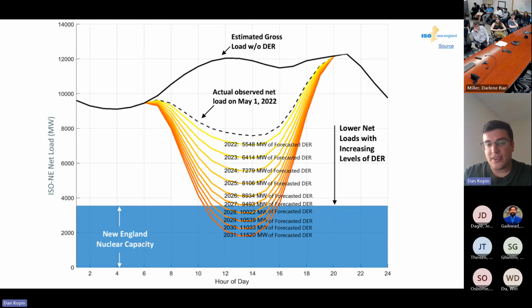What we're seeing here is that if the net load goes down in 2031 to below 2,000 megawatts, it's very likely we're going to have to do something with the New England nuclear capacity that it was not designed for. When folks have seen this slide in the past, people have said, oh, you could potentially ramp them like what's happening in France. That is certainly not what it's been designed for in terms of how New England runs those units. They run all the time, they are baseload, they do not ramp. So if these net load days show up in 2031, we have to protect our nuclear units.